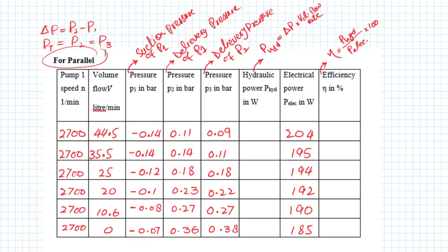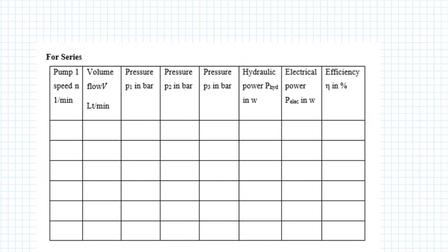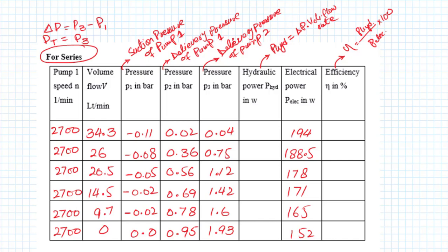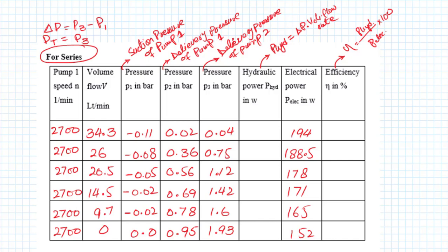In series case also, pumps RPM will remain constant. Just valve 3 will be slowly closed from fully open and we will get readings. Since this is series combination, delta P will be P3 minus P1 and total pressure will be P3.